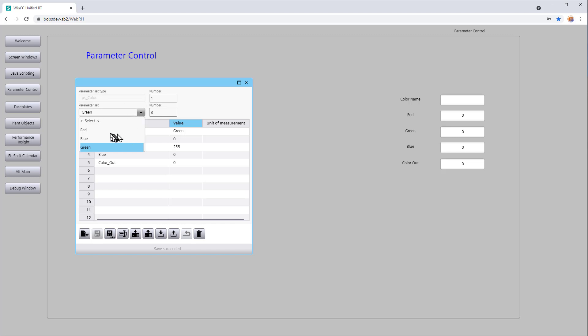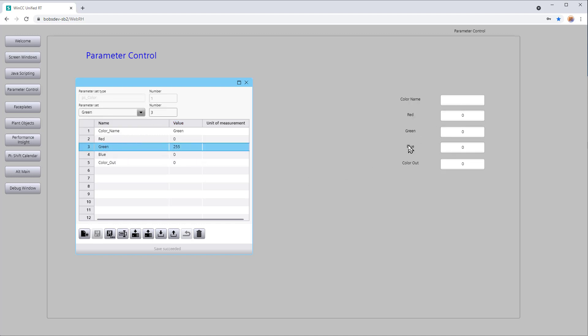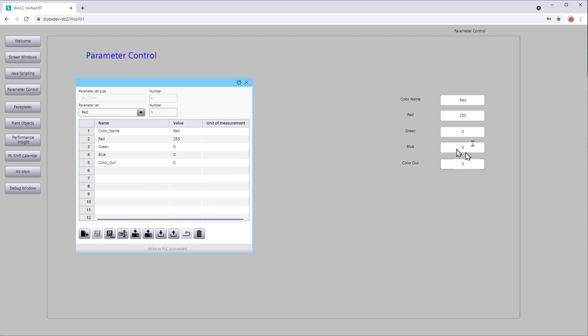Now we've got three recipes, or sets of parameters, and we can see these in the control. The UDT tags would ideally exist under address spaces in your PLC, and this is how you communicate and tell the process which color to use — this is two-way communication. So if we want to download to the PLC, we can pick a parameter set. We'll pick red and hit download — you can see it fills in the tags with the information from that record. If we go to blue and do a download, you can see it changes to blue and green. Color out is going to be the RGB value of these three components, so our next exercise is writing a script that will calculate what RGB should be and show it as a number and a color, and we'll update the records with the appropriate color out values.